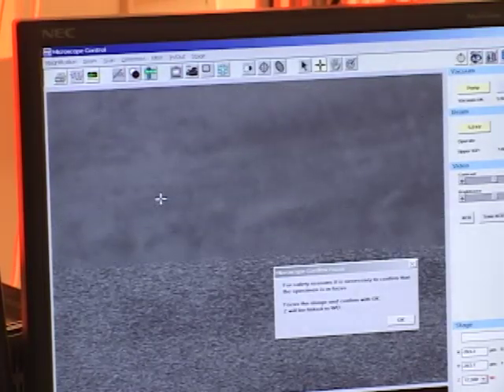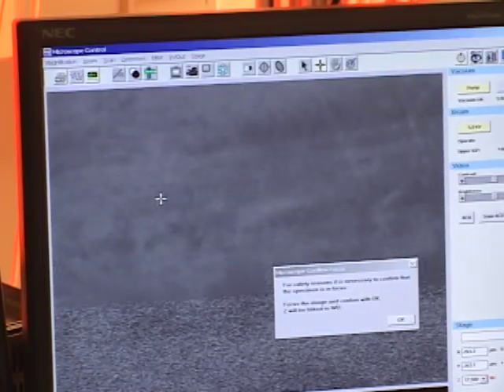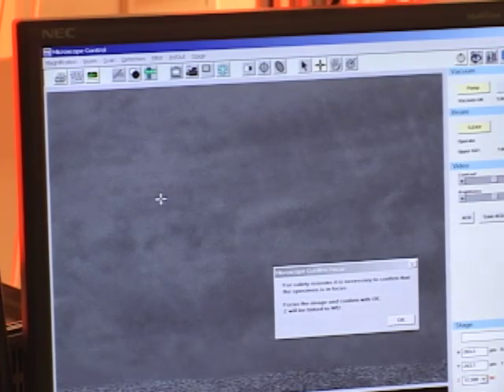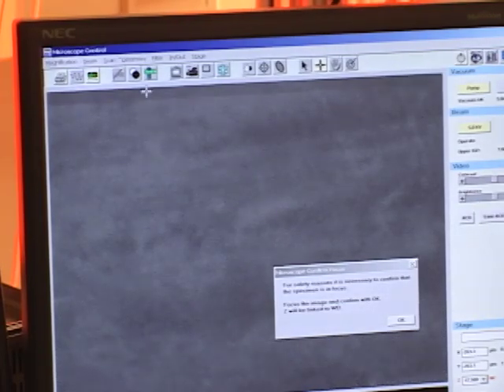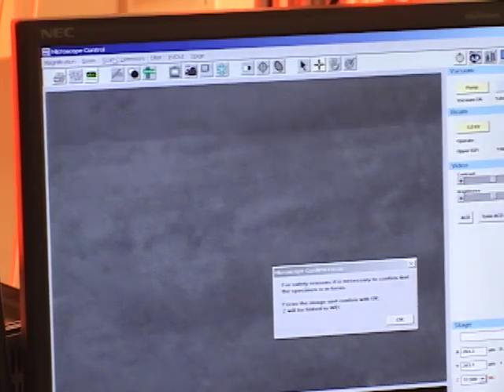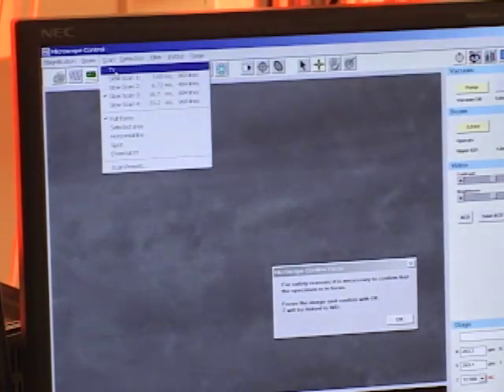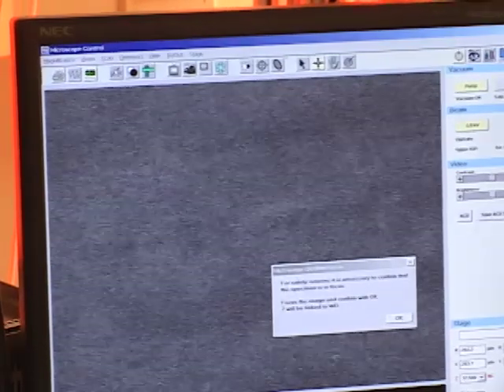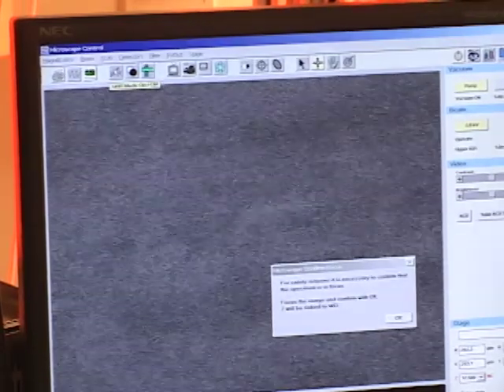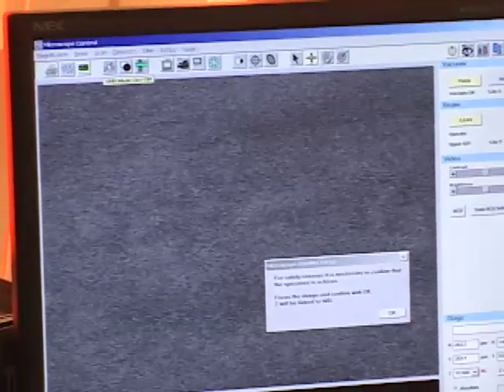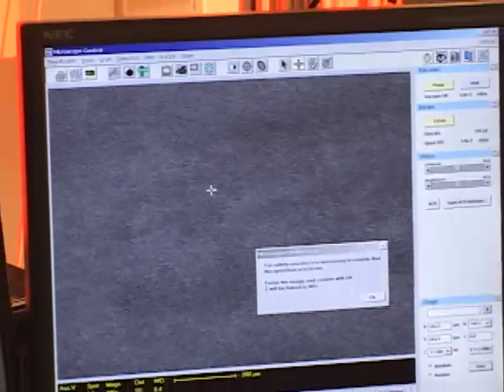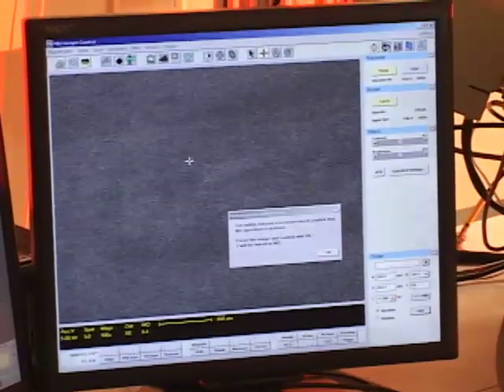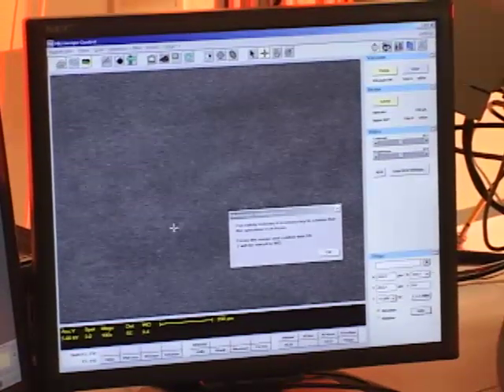Slower scan rates have a lower refresh rate, but they have a lot less noise in the picture. So as long as we're moving the sample around and we want a live update, I'll leave the scan rate on TV. When we want to do fine focusing, we'll look at a slower scan rate that removes all of this noise from the picture.